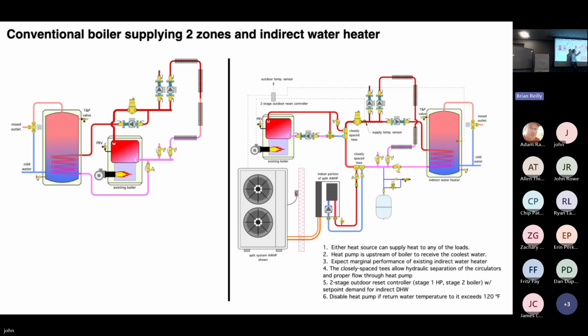If you do this, it is important that the heat pump is the upstream connection. In other words, I do not want to do this. I don't want the boiler upstream of the heat pump. Anybody know why? Think about heat pump performance as a function of water temperature. We want the coolest water into the heat pump, right? So if both of those were operating and if the boiler was down here, it would raise the temperature of the water before the heat pump, which would be up here, even sees it. It would still work, but it's definitely going to be less efficient. So always think, where can I access the lowest water temperature in the system and use that water temperature for the heat pump?